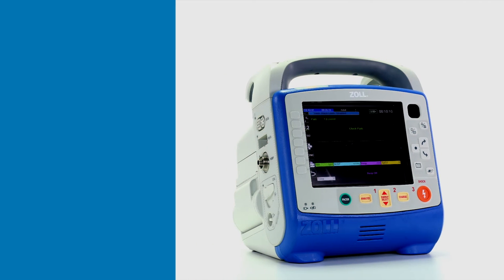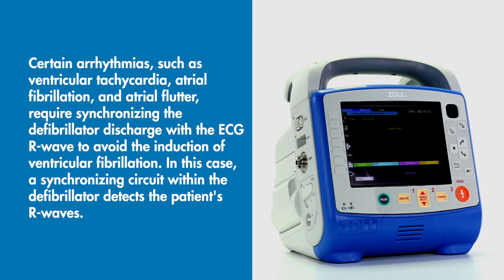Synchronized cardioversion: certain arrhythmias such as ventricular tachycardia, atrial fibrillation, and atrial flutter require synchronizing the defibrillator discharge with the R-wave to avoid the induction of ventricular fibrillation. In this case, a synchronizing circuit within the defibrillator detects the patient's R-waves.